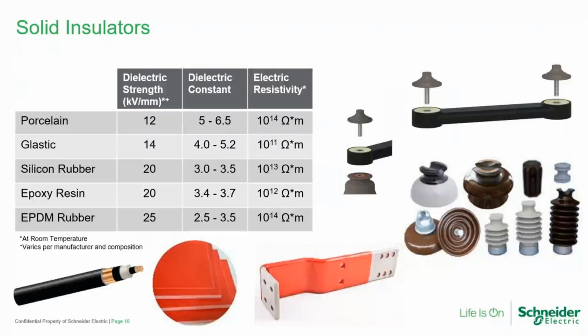All right, so let's look at solid insulating material. These are much more common and have been used for a long time in terms of types of insulators, especially in metal enclosed and metal clad switchgear. But it's important to know that when we're talking about solid insulated switchgear, we're using some of the more robust types or some of the newer types of switchgear. And these usually fall into the silicone rubber, epoxy resin, EPDM rubber styles or types of solid insulating material.